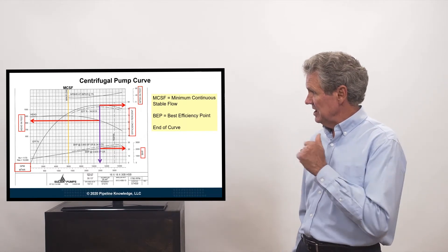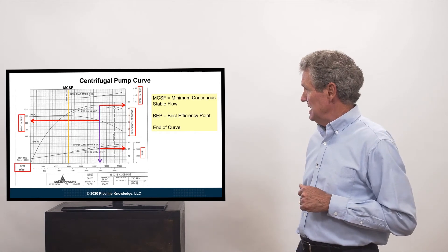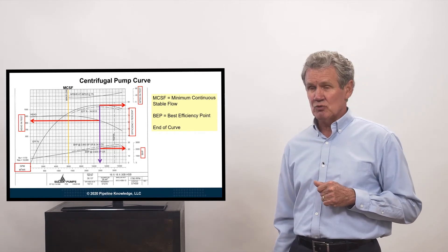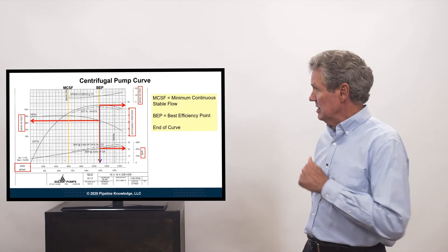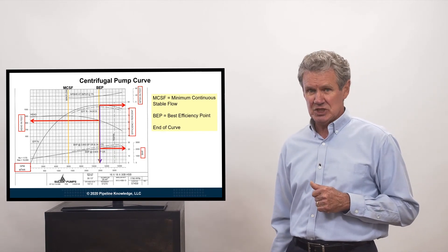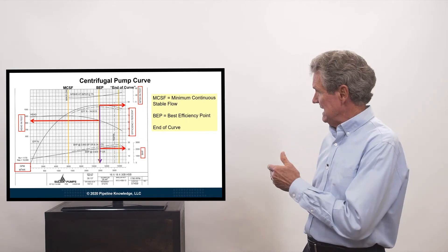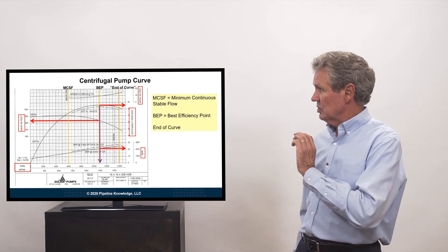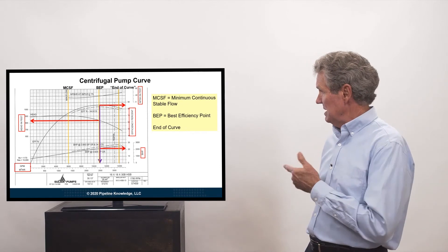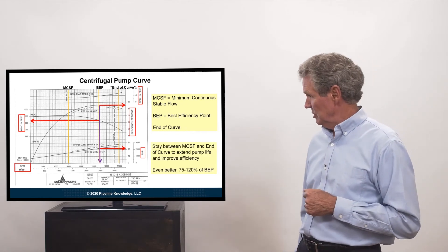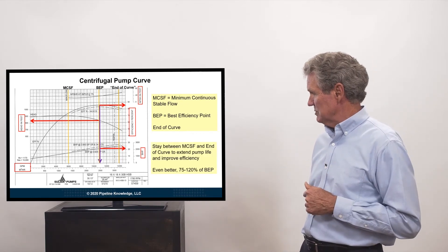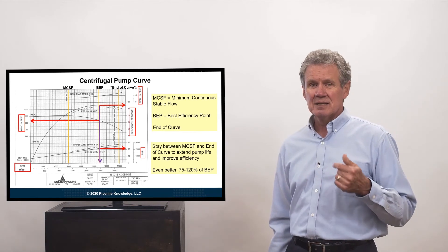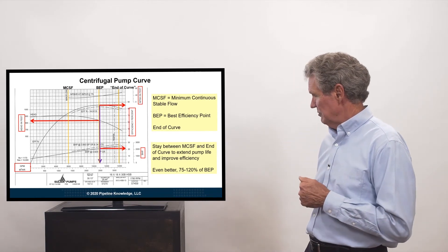So over there, where the yellow line comes down, the minimum continuous stable flow. Here, the best efficiency point. And then, we have the end of the curve. So you don't want to go off the end of the curve or go down below that minimum continuous stable flow. You want to stay between those points to extend the pump life and to improve efficiency.